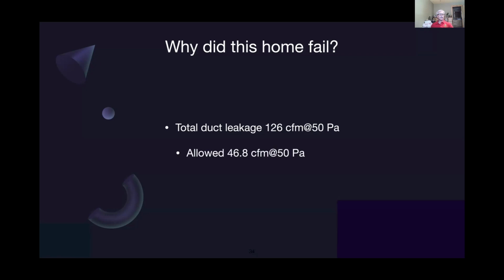And this is not a single home that they're building. These are 60 homes, all identical. So we need to figure out what's going on, stop it immediately, and correct it so this isn't happening on every single home. The duct leakage was 126 CFM at 50 Pascal. I know standard testing is 25 Pascal, but in the Pacific Northwest, with the programs we use, we test at 50 Pascal. Allowable leakage was 46.8, so that fails.